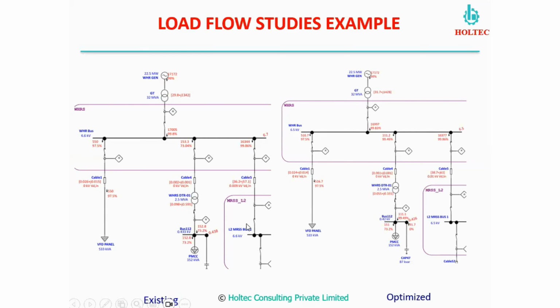So overall effect you see here, it is 152 K. This is actually kVA. All these parameters are shown in kVA and PF. So this is 152 or 153 kVA, which was the load drawn by the load, has been reduced to 111 kVA. So this much amount of saving will be possible if we optimize power factor and the voltage. But not only this, here you see this 6.7 kV, we have optimized to 6.5 kV, and this is also giving some benefits. So this is the thing.